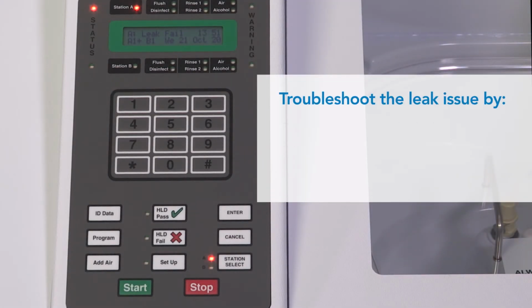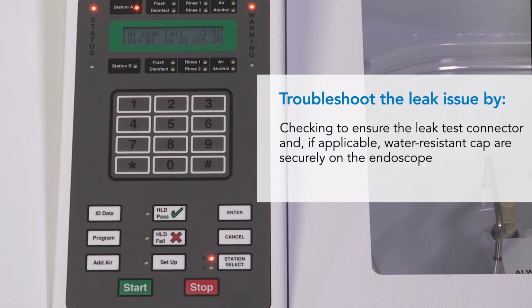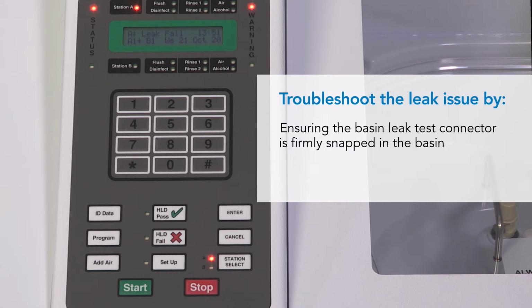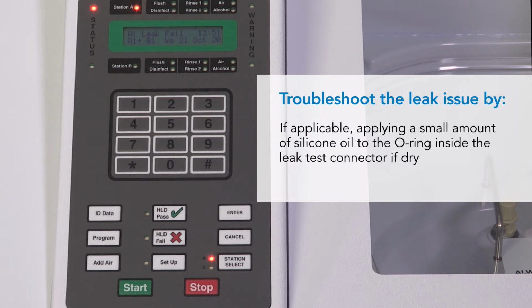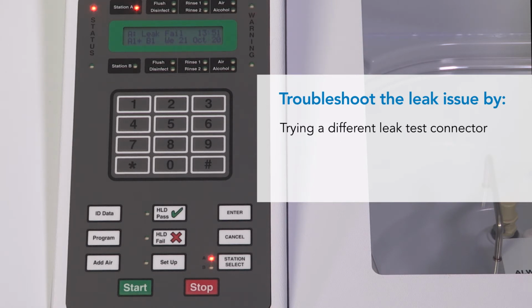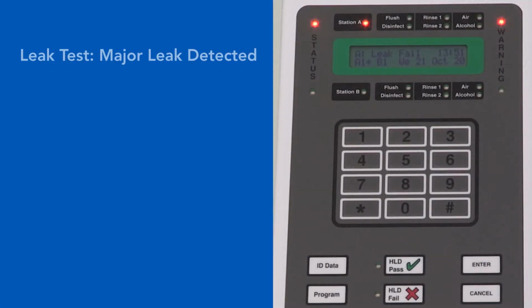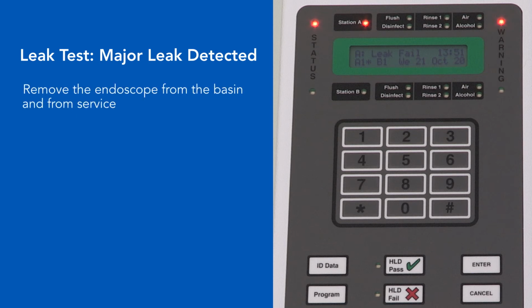Troubleshoot the leak issue by checking to ensure the leak test connector and, if applicable, water-resistant cap are securely on the endoscope. Ensure the basin leak test connector is firmly snapped in the basin. If applicable, apply a small amount of silicone oil to the O-ring inside the leak test connector if dry. Try a different leak test connector. Restart the cycle. If a major leak is still detected, remove the endoscope from the basin and from service.